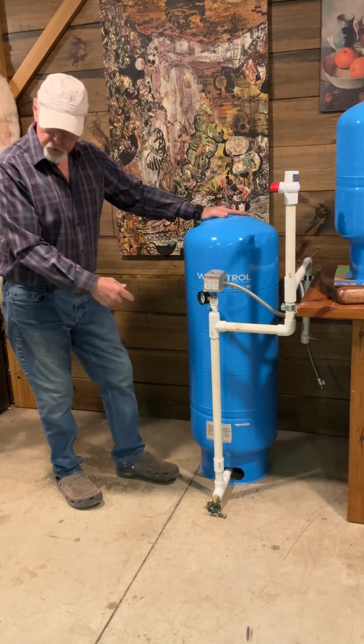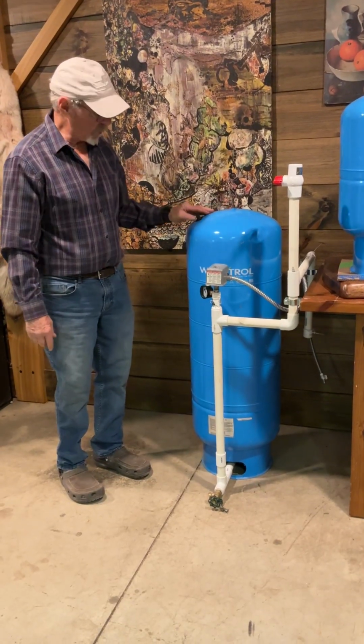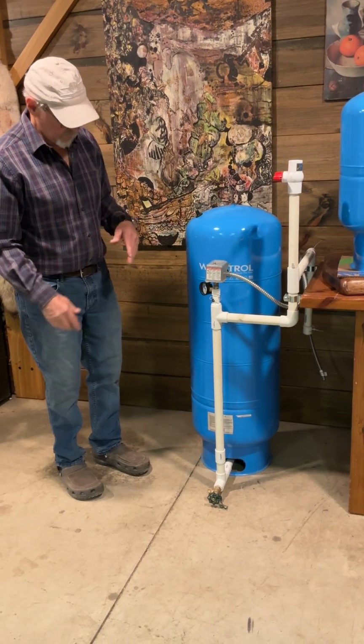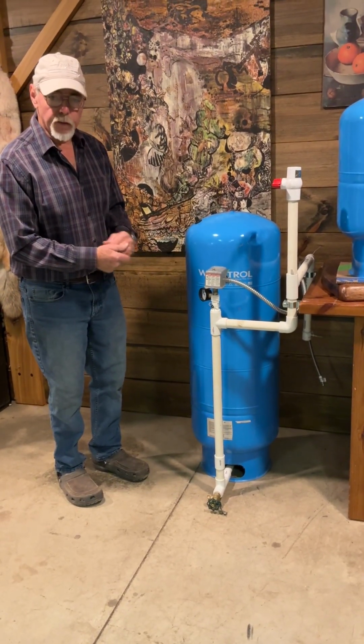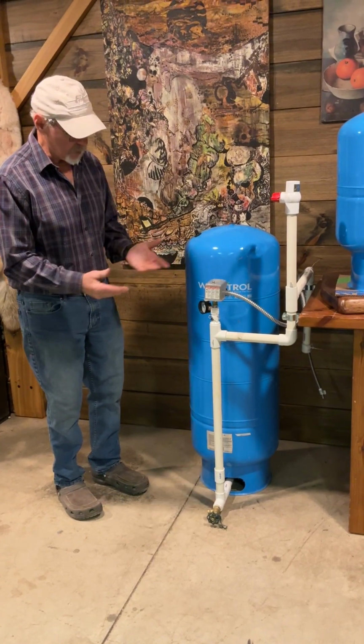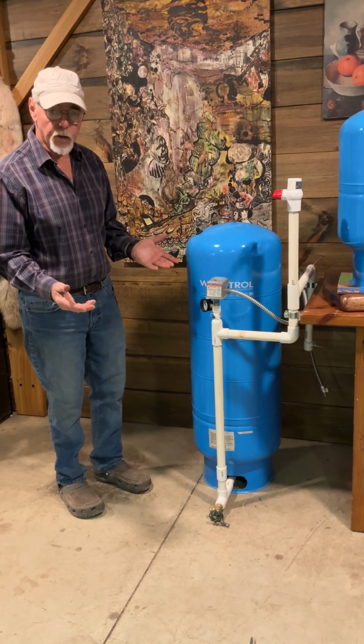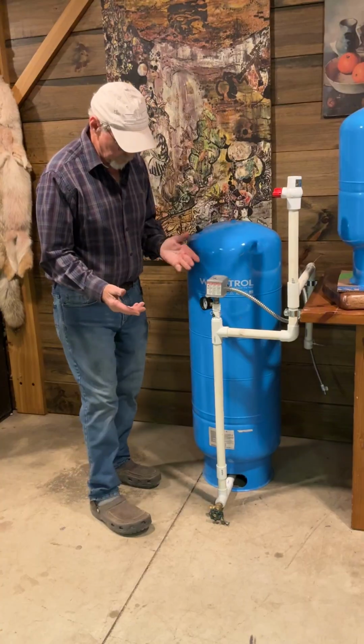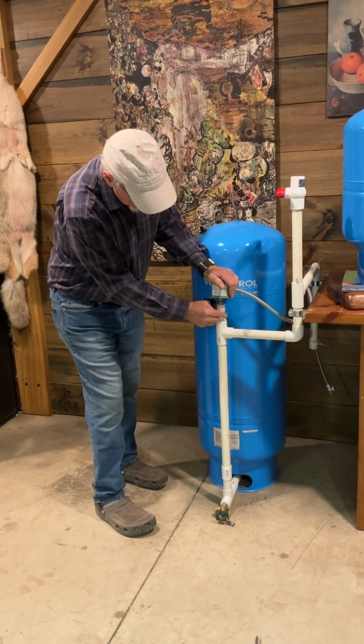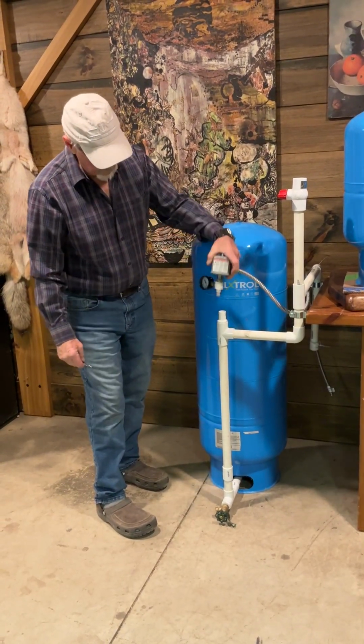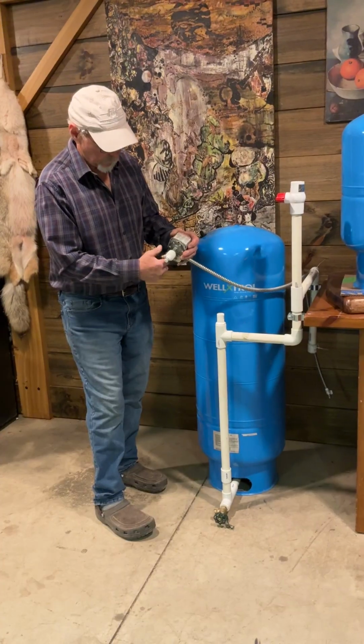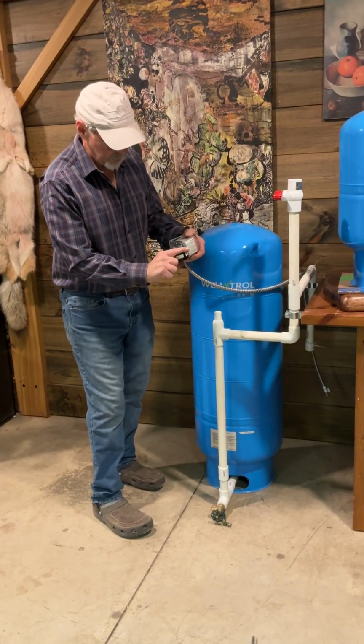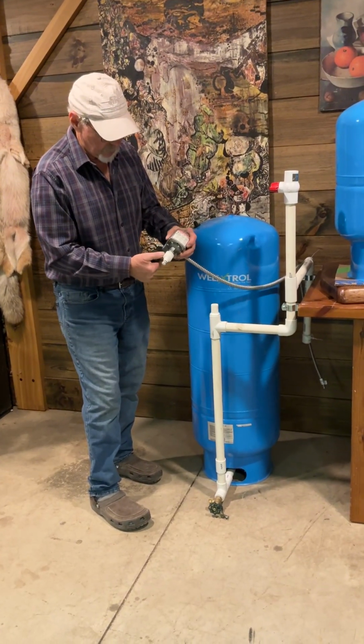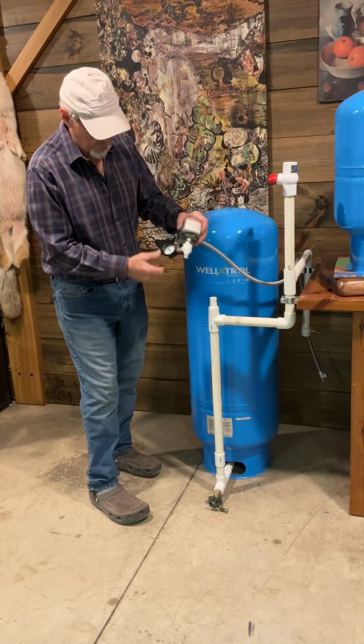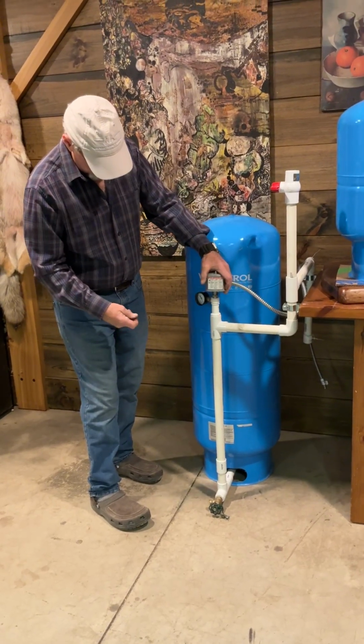You've got to get a hose on a boiler drain and get it draining so you can check the bladder pressure. But then taking the switch off a nipple, or the gauge out, you've got to contain that water too — it's kind of a pain. But with this here and that check valve, when you open it up like that, it's super easy to undo the wires, take it off, put a new one on, same with the gauge, and plug it back in.